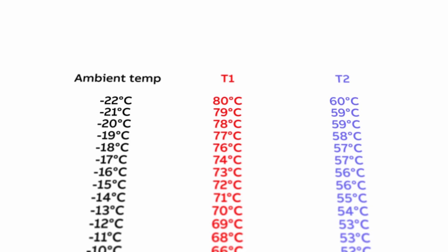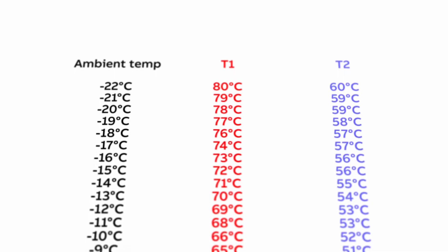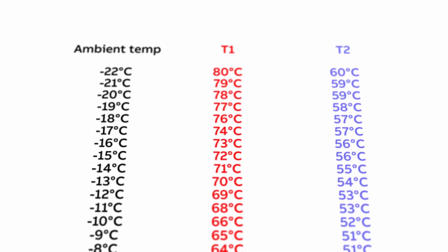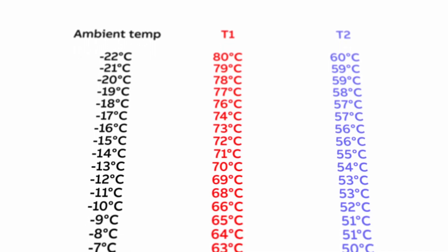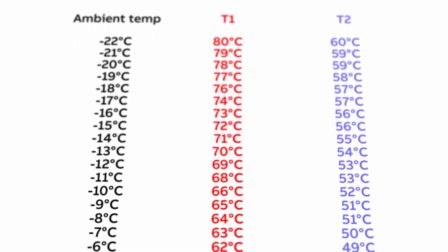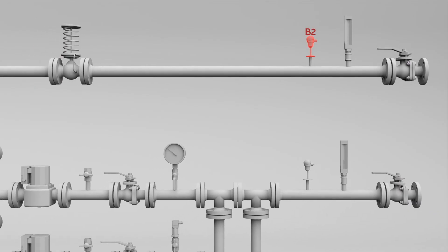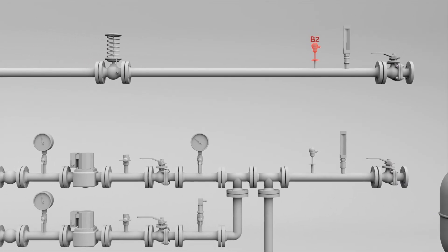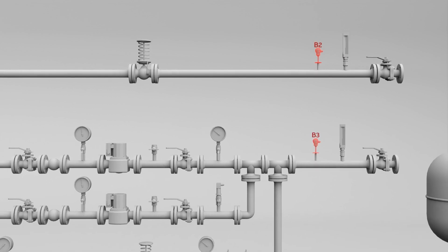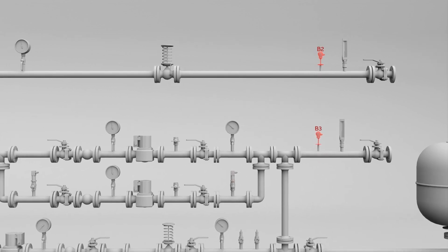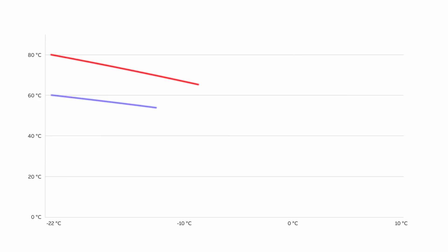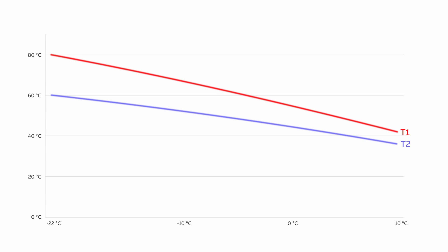In many cases, a temperature graph is used for that purpose. Basically, it is a table where for each ambient temperature value, there are corresponding T1 and T2 values. T1 is the desired temperature of supplied water and T2 is the desired return water temperature. If you put ambient temperature on the x-axis and T1, T2 on the y-axis and connect the points, you'll get the temperature graph.